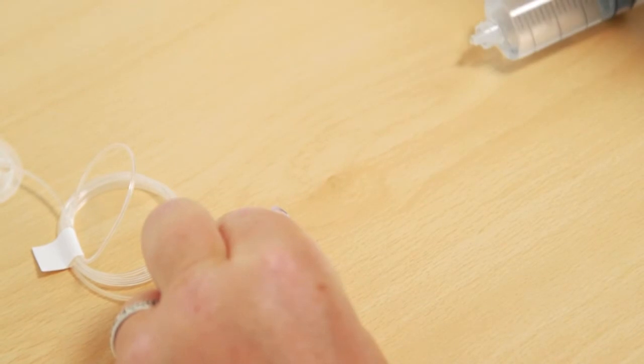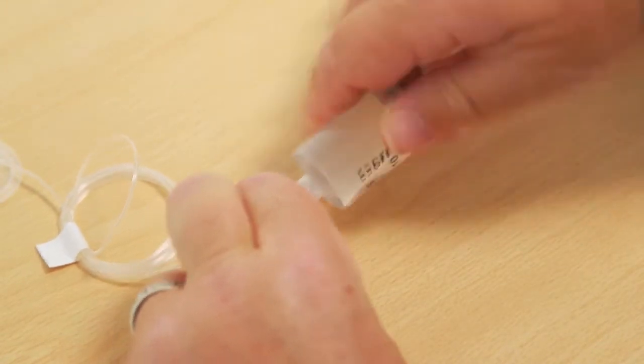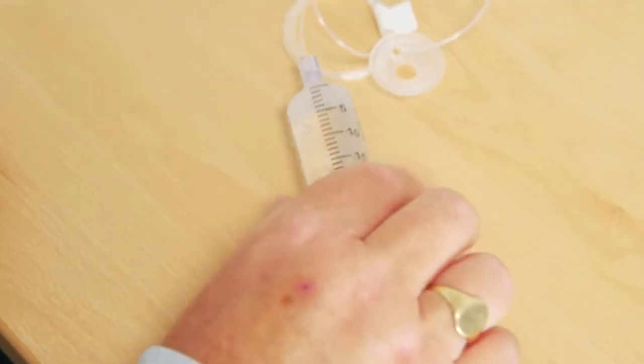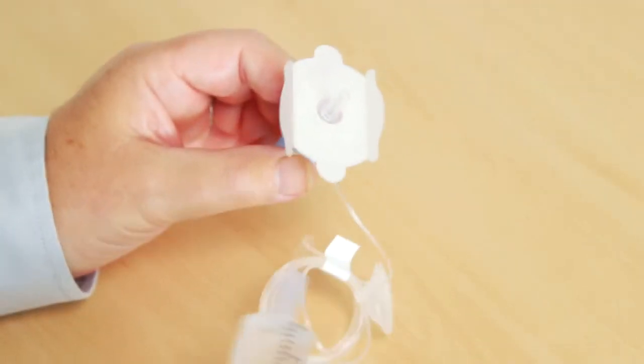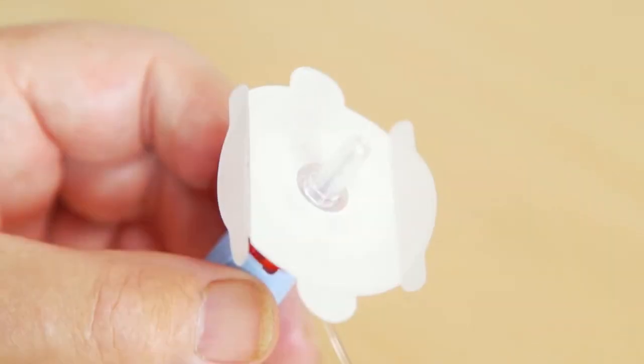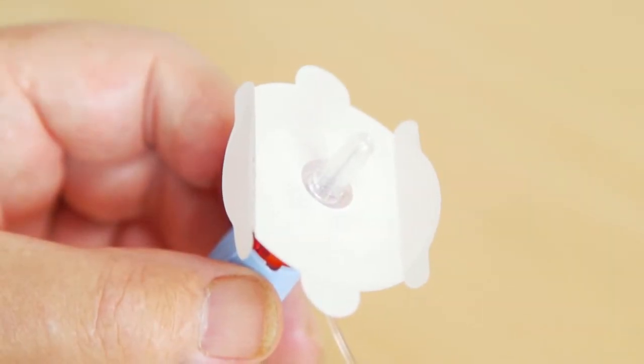The next step will be to prime the infusion set. You should note that the priming volume on these devices is very low at less than 0.2 of a mil. Priming should follow the instructions in the syringe driver's user manuals or any local instructions that are in place for this procedure. For the purposes of this demonstration, I will prime the infusion set manually using a syringe. Carefully advance the syringe until you see a small drop forming on the tip of the needle. Because of the very low volume required, this will occur very rapidly.